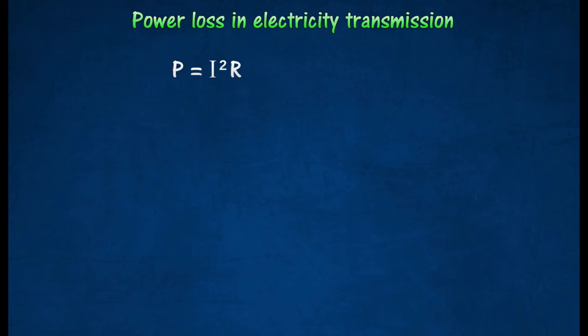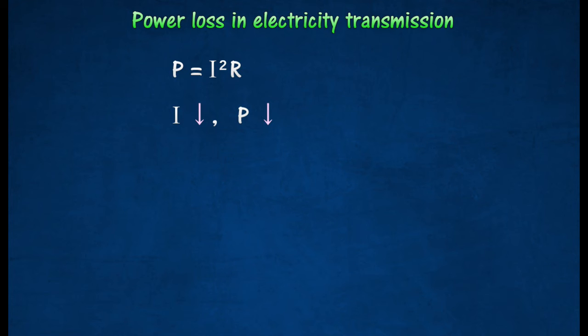The formula shows that the power loss during transmission is directly proportional to the square of the current flowing through the cables. The power loss during transmission can therefore be greatly reduced if the transmission current is reduced significantly.